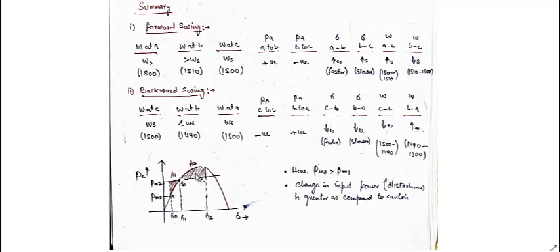Earlier value was slightly like this. We can say now the accelerating area is more, so the decelerating area should also be more, so that this area should be equal to this area. In other words, this delta has to increase further so that this speed will be decreased, because for this case it needs a good amount of decelerating power.